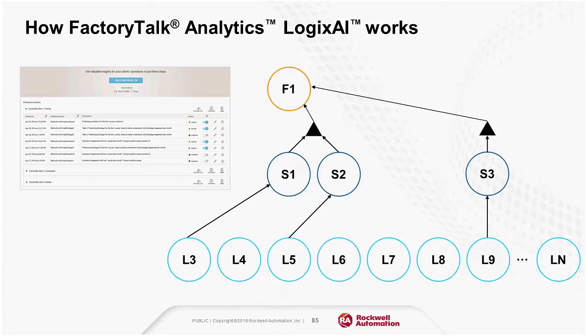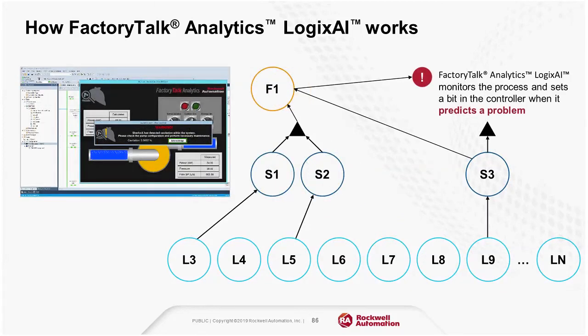Once you identify outputs and inputs, Logix AI watches the running operation and trains itself unsupervised, observing data streaming through the controller. The module finds correlations, thins the data, and builds a model. The predictive model building process is fully automatic — Logix AI rapidly formulates theories of potential mathematical models of your observed operation and tests each until it is confident it has selected the best possible physics-based model. Training time varies by complexity, but in a simple process unit 20 to 25 minutes of unattended training is common. Once ready, Logix AI triggers a bit in the controller to indicate it is ready to begin predicting, and a UDT (user-defined data type) is made available that, once imported into the controller, will be updated by the model with its predictions.